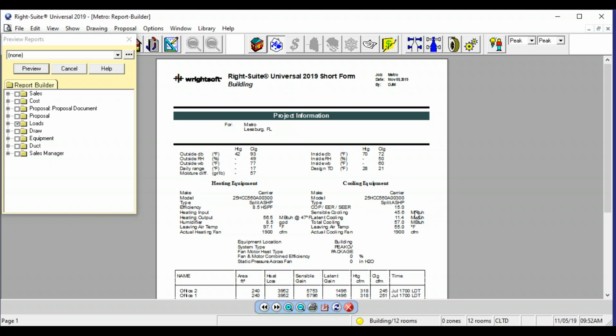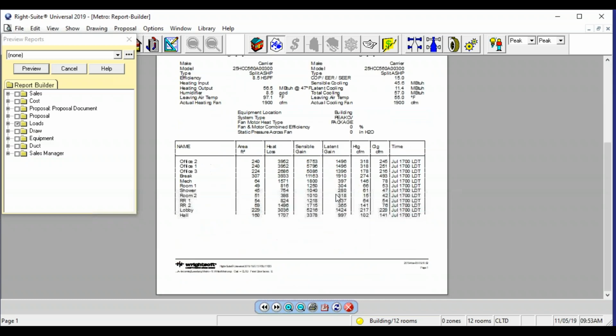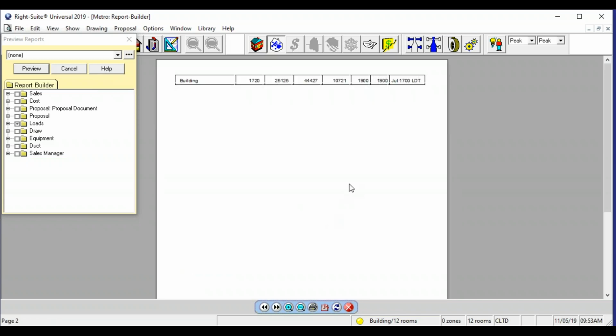And when I do a commercial design, I always like to make sure that my sensible and my latent are both sized with the unit. I know in some areas of the country, I'll do that with the residential as well. If I was to do this in Florida, Florida building code states that it's the total and the latent, so the sensible isn't worried about as much. In Florida, we're worrying about that moisture removal inside of a home, and then we're also worried about making sure that the overall capability of the unit can satisfy any type of requirements that the home has. But that's on residential. Commercial is a completely different monster, so that's why I like to make sure that sensible and latent fall within all those parameters. And so we do. It looks great, and I'm going to go ahead and move on from there.